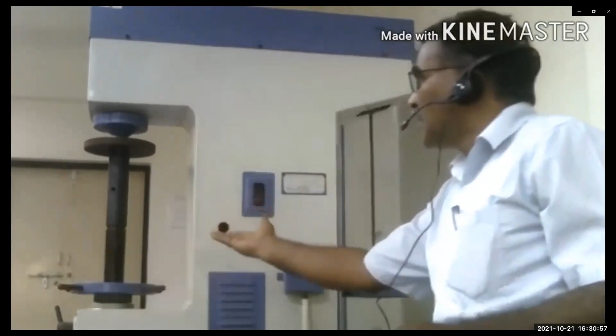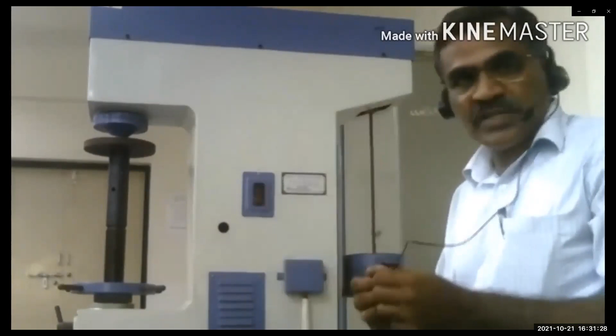Now we have to apply the load. In the previous case, with the Rockwell hardness, we applied the load slowly with no time limit. But here there is a time setting: the load has to be applied for only 15 seconds. You switch on the timer, apply the load, and exactly at 15 seconds you stop it and unload.